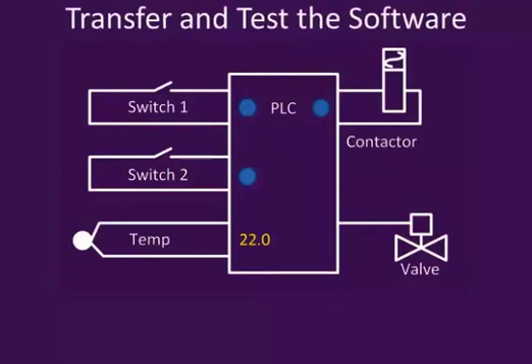Now we transfer and test the software. You should already have tested the software in simulation mode, so now we just need to marry the software to the hardware. So you check the software assignments match the actual hardware. That means that where the software says input 1 is switch 1, that it's actually correctly wired up.